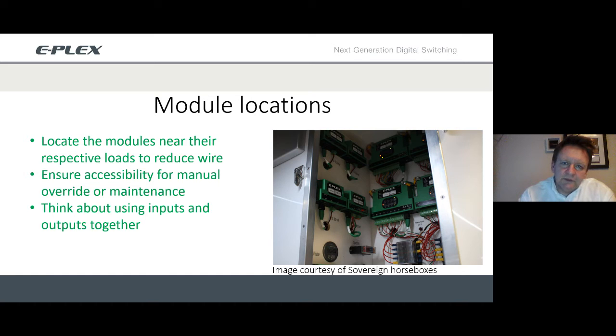The modules that we use for the lighting control, device control, the switching modules all have a manual override capability, so that if there is some kind of network problem and there is no communication going to the modules, you can get to them, you can still turn on your lights, the circuit breakers inside the modules still operate fine, and you can still control all the devices that you need to.